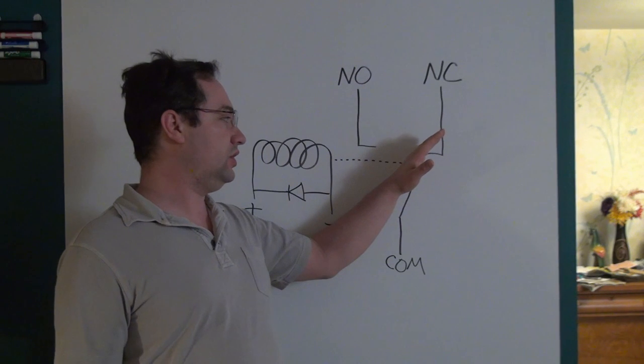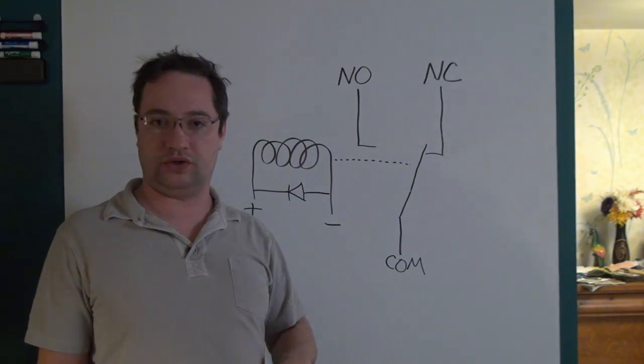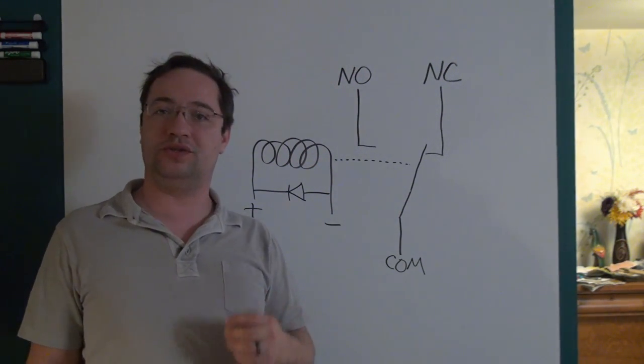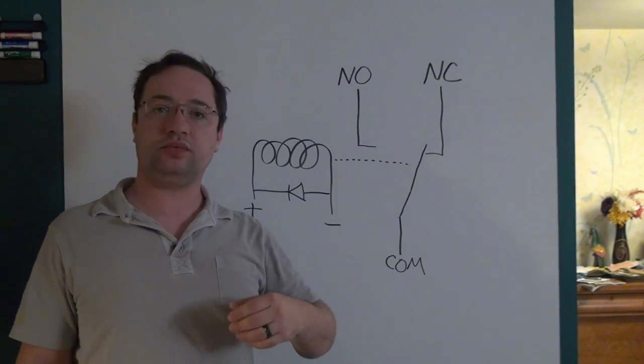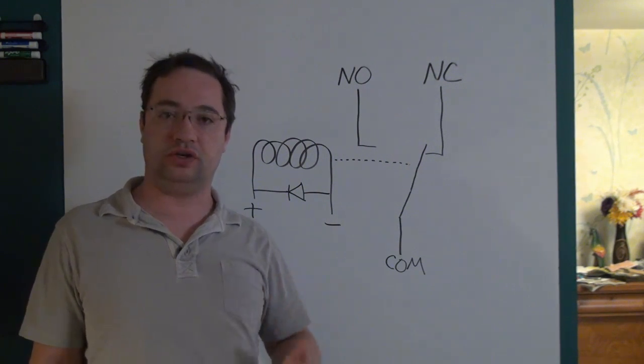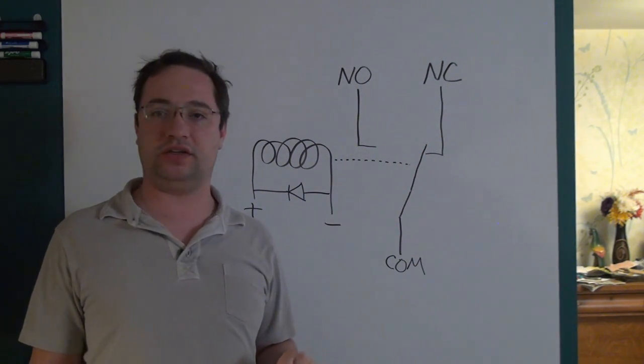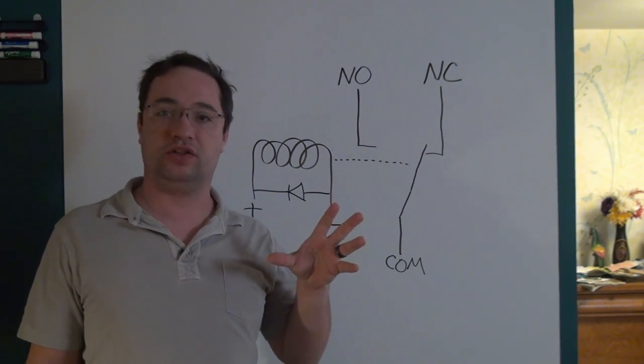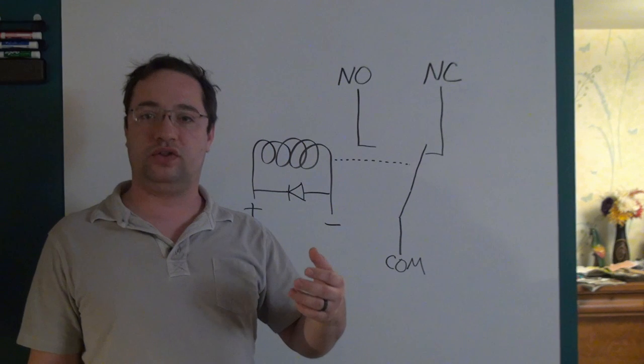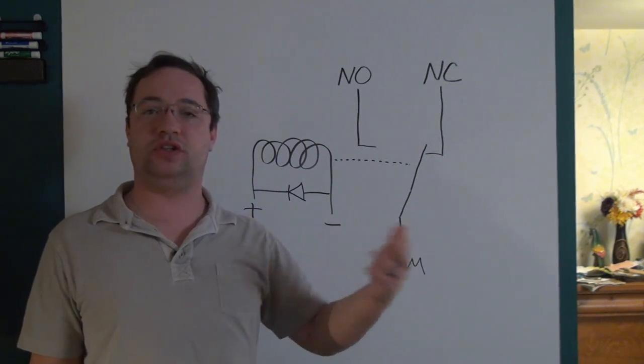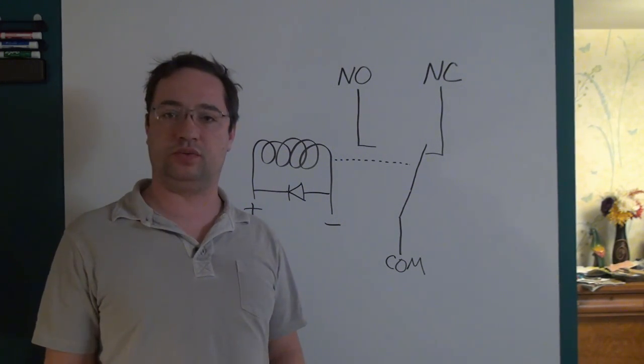If you're using DC and current is flowing, when the contact starts to move, the DC current will continue to flow until the gap between the arm and the fixed contact becomes large enough that it can no longer sustain the arc and the arc goes out. But this time is substantially longer — probably by an order of magnitude — than what happens with AC.